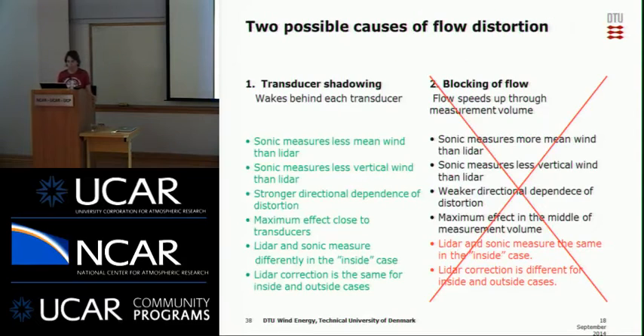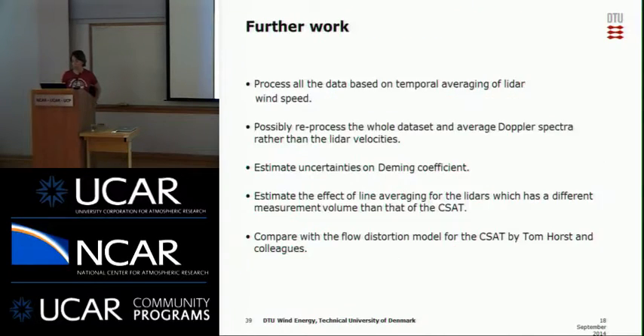So if we look back to this list we made, it seems like it's transducer shadowing that causes the flow distortion to the instrument, or it's the main cause. Now I need to look at more data, and maybe we will even reprocess the whole data set, because we have 60 Hertz data in the LiDAR, but if we need to average for reasons that Jakob will talk about in a minute, then it's actually better to average on the Doppler spectra than on the velocities. So that could help us avoid some noise.